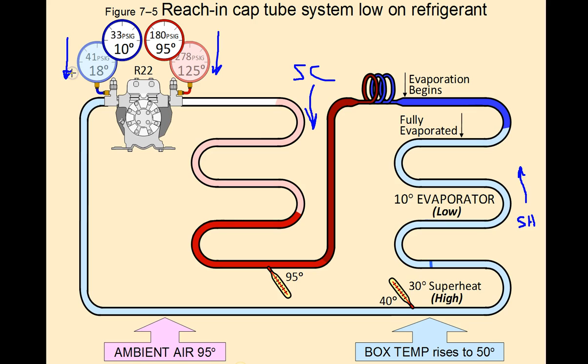This is a classic example of an undercharged system with a fixed metering device. Now, how do we know they didn't just put hot product in the box, causing the box temperature to rise? The way you know is because the sub-cooling of the system would be normal even if we had hot product in the box. So it's the low sub-cooling and low pressures that are your key indicators of an undercharged system, along with being able to visualize and understand what's happening within the refrigeration system itself.